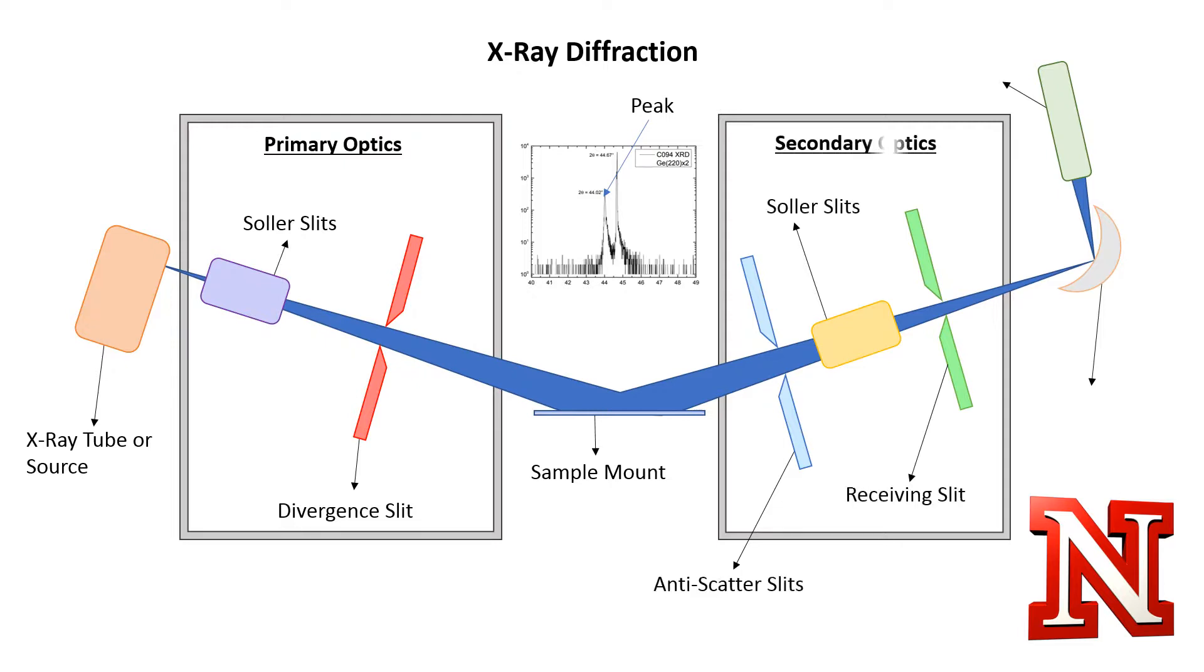Secondary optics receive deflected rays. Monochromators filter out unwanted x-rays. The detector converts x-rays to visible light, which is called scintillation. X-rays contact a compound that absorbs x-rays and emits visible light, then produces proportional electrical voltage.